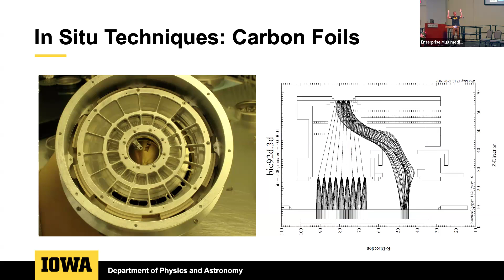And actually, with high probability, it will knock some electrons off of the carbon atoms in the foil, and it will create an electron pulse. And you can then use that electron pulse as a start time. So your ions come into the aperture here. They go right through and come on down to the bottom. But when they go through, they generate some start electrons, which you steer over here. The electrons move so fast that you can basically measure this pulse of electrons and call it your start time, and then you measure when the ions get down here and you measure your stop time. That gives you a time, that gives you a velocity. With a velocity and an energy, you get a mass, and voila, you have everything.